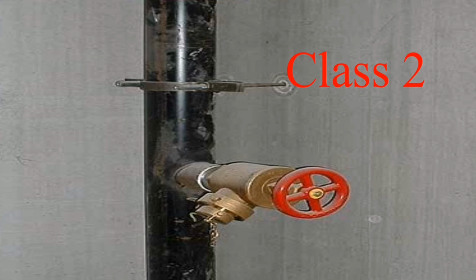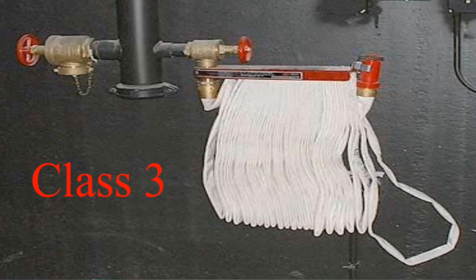Class 3 systems shall provide 1-1/2 (38 mm) hose stations to supply water for use by trained building occupants and 2-1/2 (64 mm) hose connections to supply a larger volume of water for use by fire departments and those trained in handling heavy water streams.